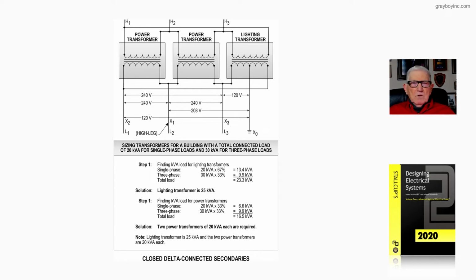Based upon utility voltage, or however you're obtaining your voltage, your power supply, if it's high voltage or a little low, whatever it may be, that determines the high leg. Usually the high leg's about, in most cases, about 194, 198, something like that, based upon voltage drop and the run of the service conductors and so forth. But basically, this figure 20-2A shows how to size those transformers.